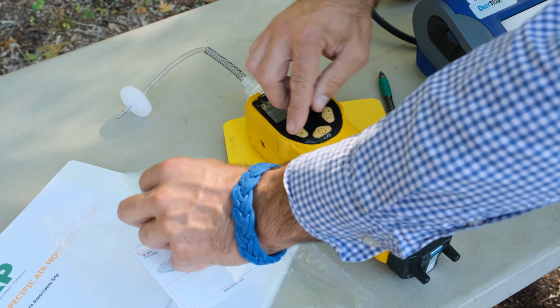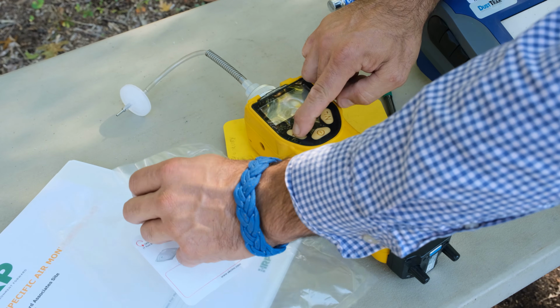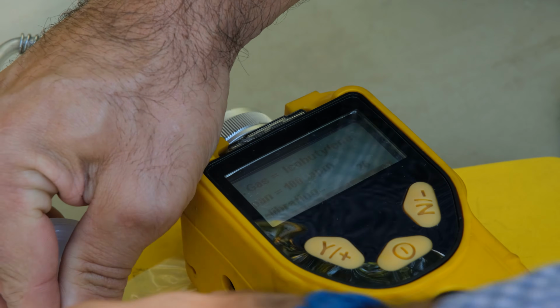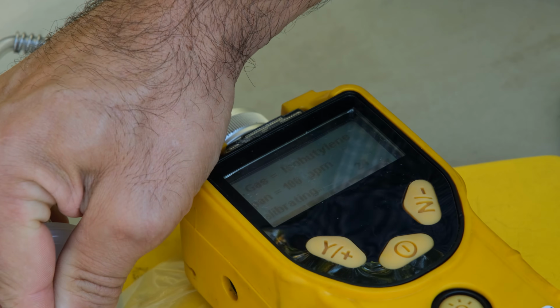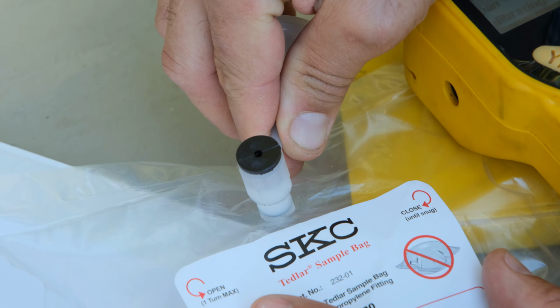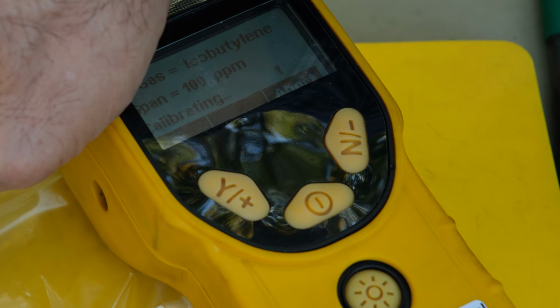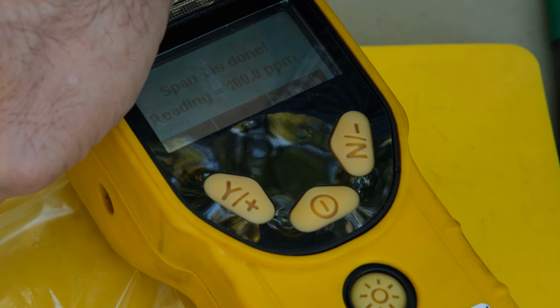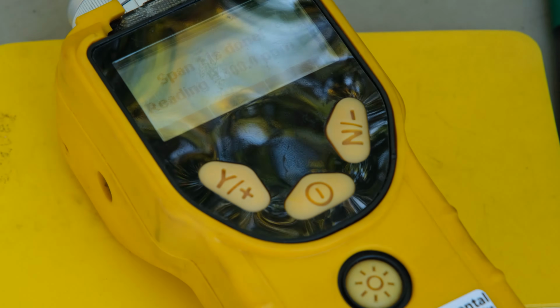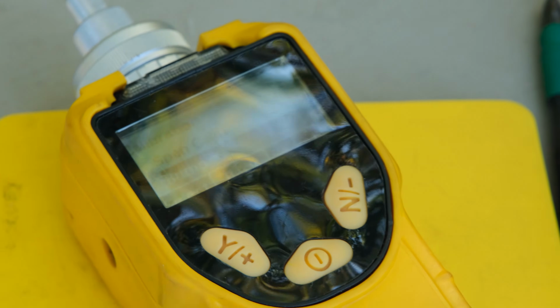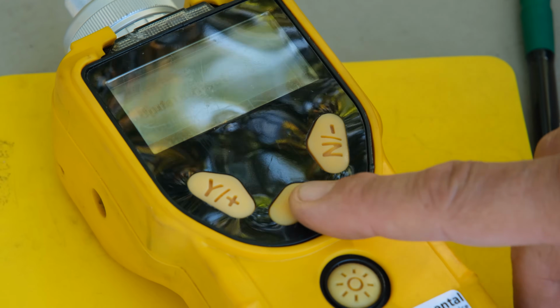We're now going to enter span calibration, and we'll set that up using the isobutylene. Again, you'll find span calibration in the menu and select it with the same button. You go ahead and attach your Tedlar bag. Very gently, you'll push a little bit of isobutylene through the sensor. All right, you want to get about 100 ppm to be calibrated. When you're all set, you'll get a nice little message on the screen. Once you're done, you can go ahead and hit that center back button. You then let the PID purge for a minute.